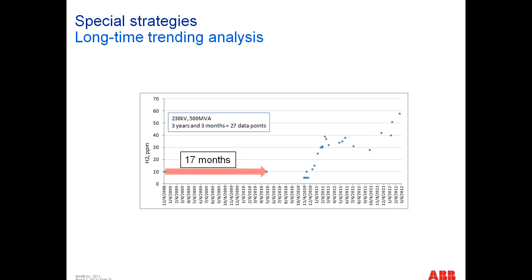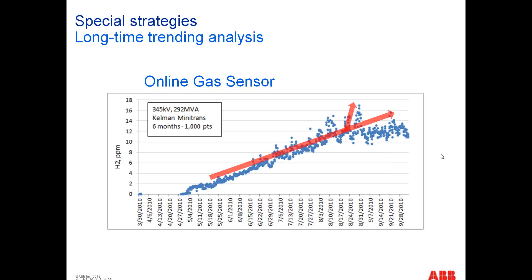If you simply take a look at two points, you don't get much of a trend. But as life goes on, you follow that data and say, okay, there's an increasing trend, but it's relatively flat. It accelerates in the summer, when literally our peak demand typically happens in North America and we see the highest temperatures, and backs off a little in the winter. But if we start taking action without knowledge of the long term, we might assume something bad is going to happen with this transformer, when in reality, when you look at the data, the transformer is pretty normal—it just had a hot August where some high gas was collected.